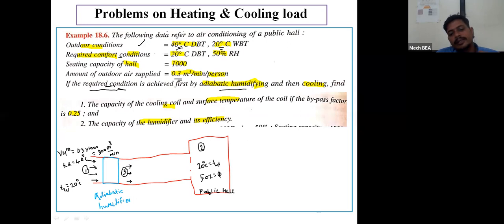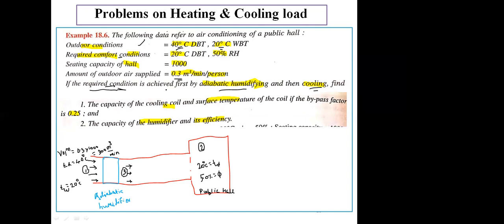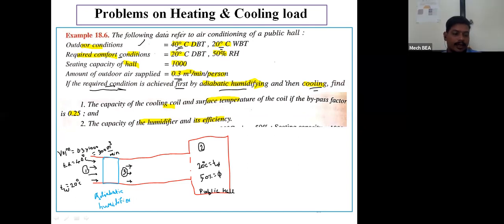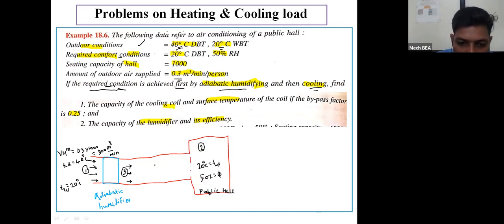But here, as they have provided the adiabatic humidifier, it is not necessary to take point number 4 for that adiabatic humidifier. Whatever the outlet of that adiabatic humidifier will be, that will be supplied to the cooling coil. Here you can see the required condition is achieved first by adiabatic humidifying and then by cooling. As there is a cooling process, we have to have the cooling coil. So here we'll represent one coil as a cooling coil. Suppose this is a cooling coil.